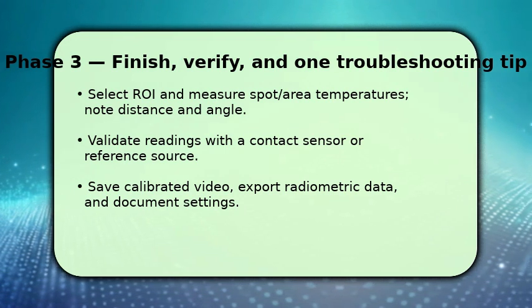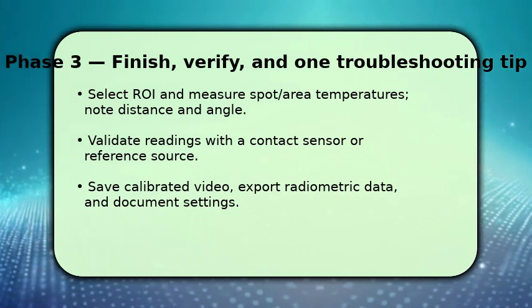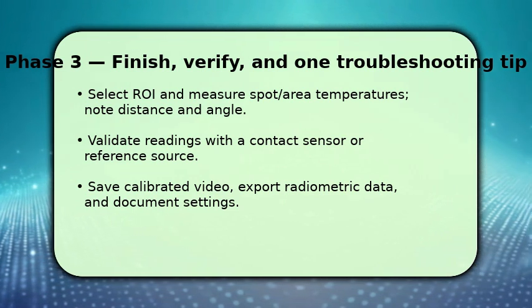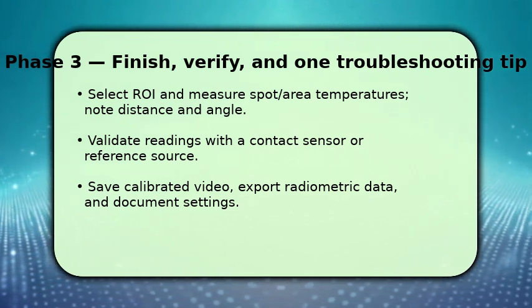If readings drift or show bands, run another NUC and recheck emissivity. This troubleshooting step usually resolves artifacts.